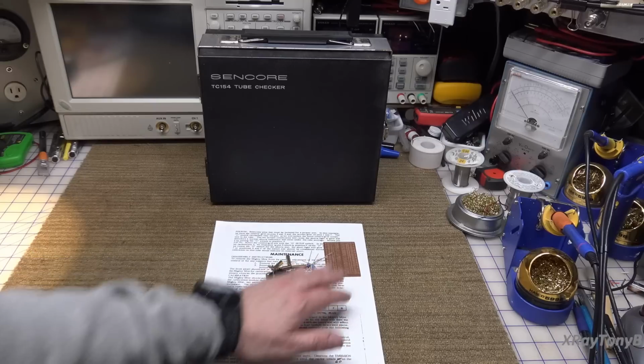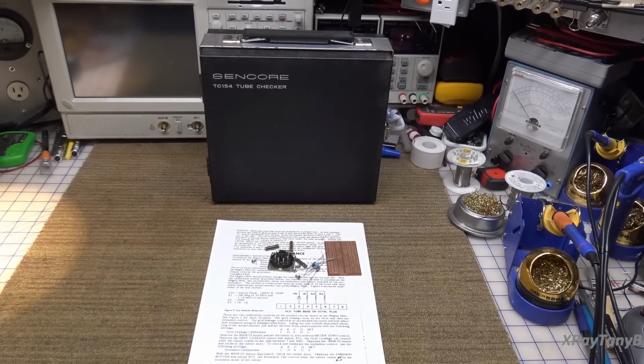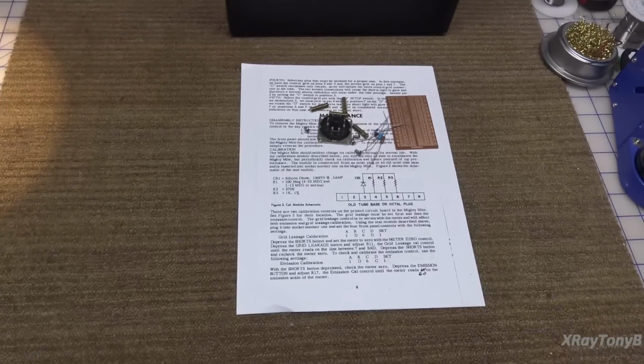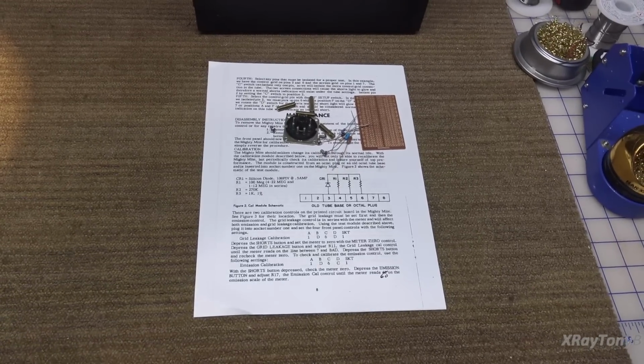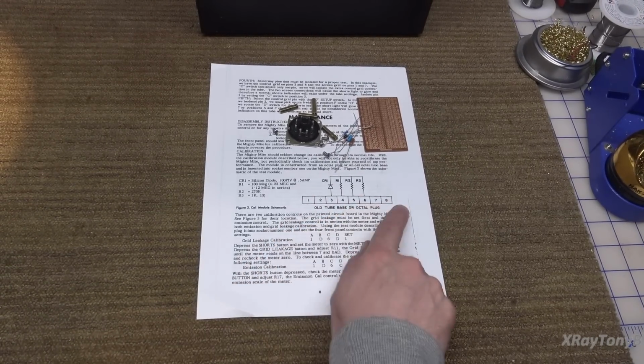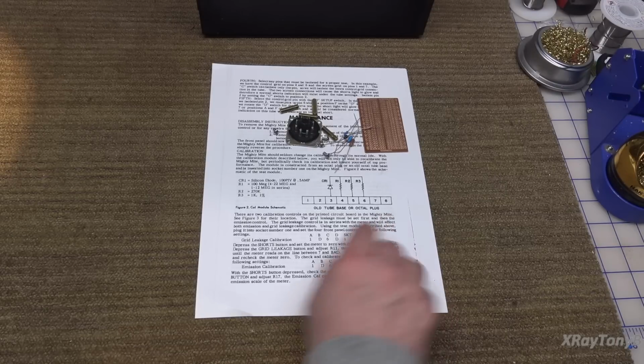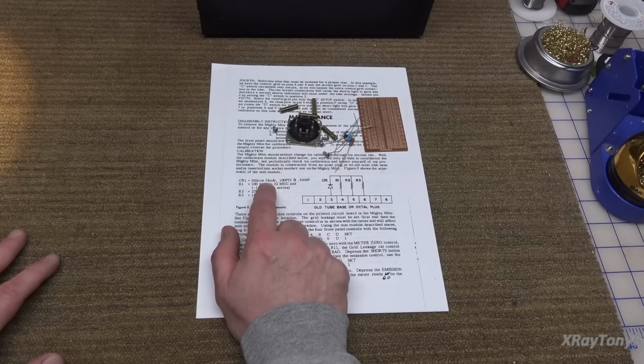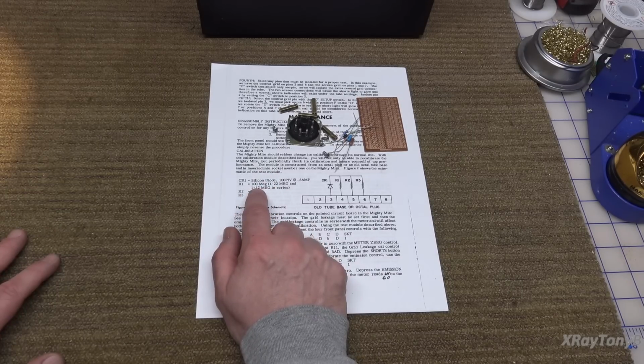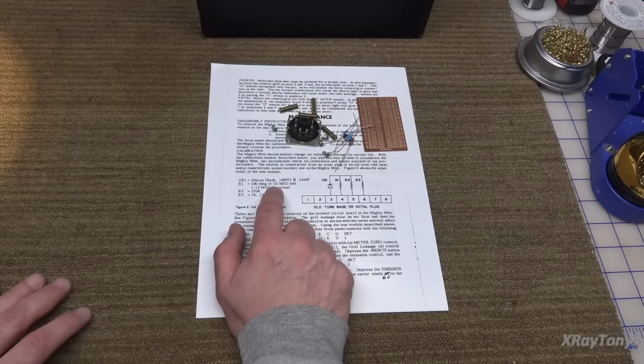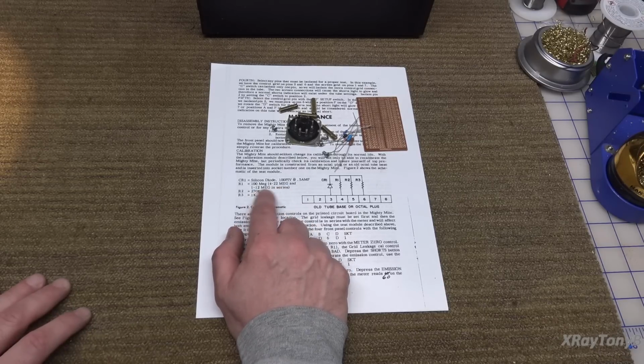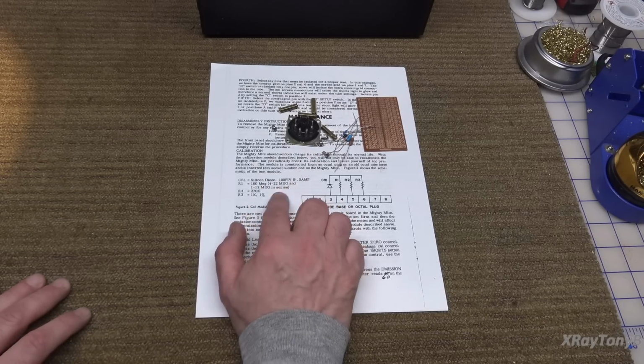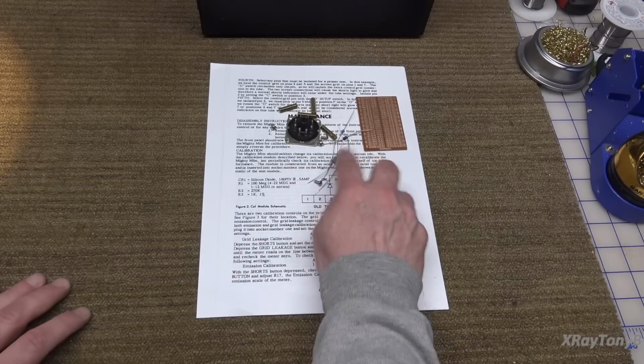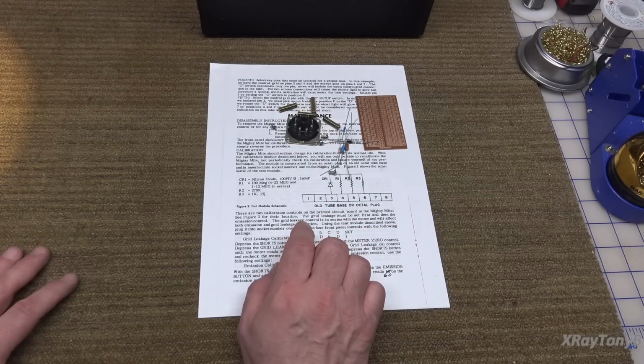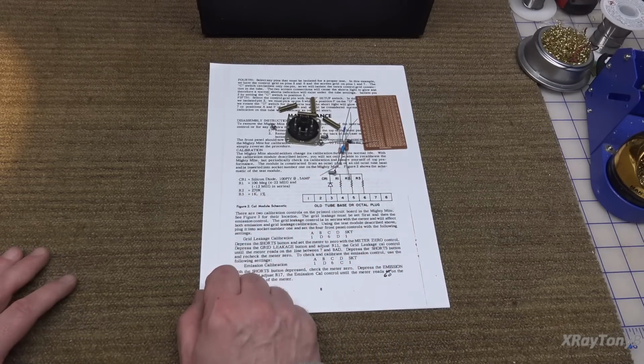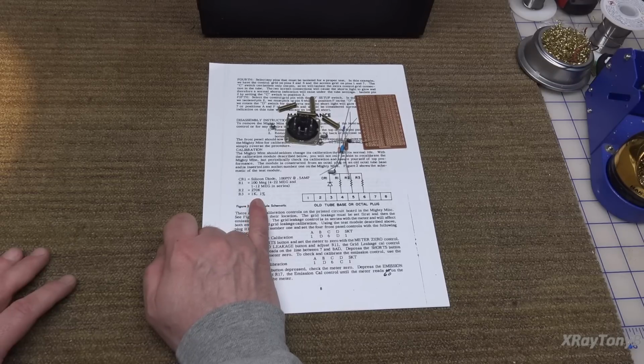And all of these units, they give you an instruction in here, and I've printed it out from the service manual, how to make your own calibration jig. And you only need a few components to do this, so I'm going to make one. You can see they're just showing an 8-pin octal socket, and then you need a diode, just a silicon diode, a 100 meg resistor, which those are kind of hard to come by. They want you to use 4 22 meg and 1 12 meg all in series, but I actually have a 90 meg and a 10 meg that I can put in series, and we'll test those here before we install them. They want a 270K resistor and then a precision 1K 1% resistor.